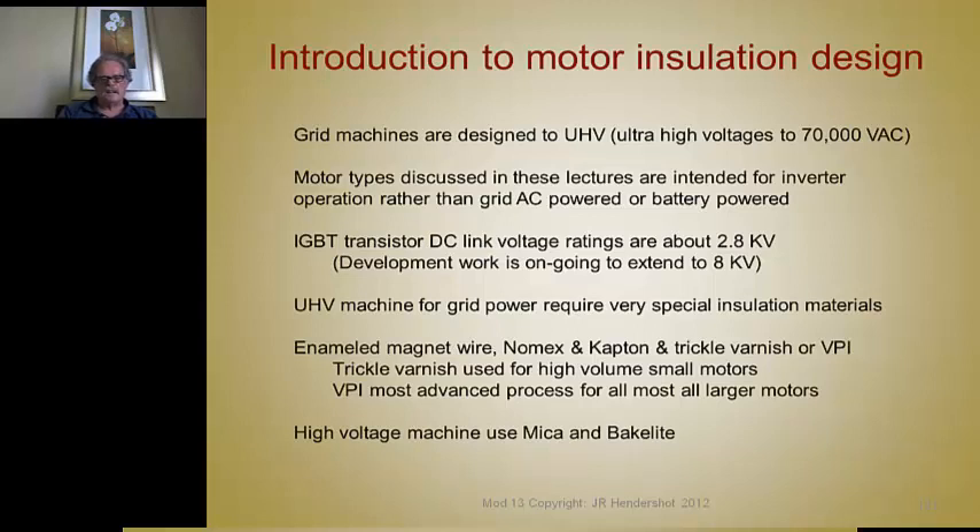For the machines we're going to talk about, we use enameled magnet wire for insulation of the magnet wire from conductor to conductor, turn to turn. And then Nomex and Kapton slot liners, and then varnishing using VPI or trickle varnish techniques.